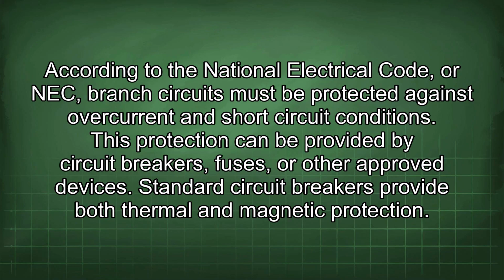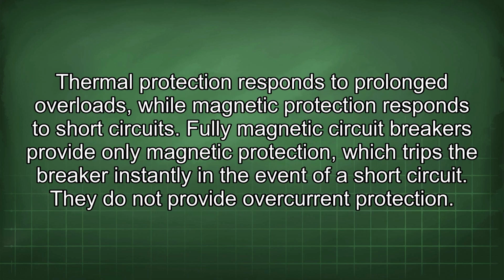According to the National Electrical Code, or NEC, branch circuits must be protected against overcurrent and short-circuit conditions. This protection can be provided by circuit breakers, fuses, or other approved devices. Standard circuit breakers provide both thermal and magnetic protection. Thermal protection responds to prolonged overloads, while magnetic protection responds to short circuits. Fully magnetic circuit breakers provide only magnetic protection, which trips the breaker instantly in the event of a short circuit. They do not provide overcurrent protection.